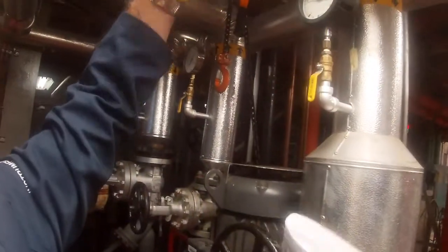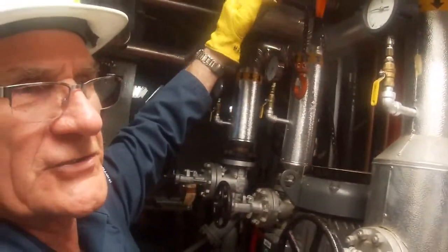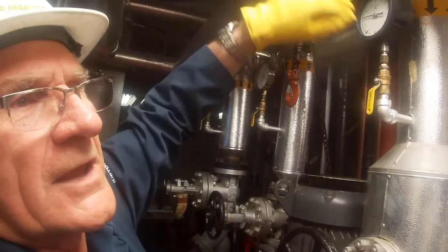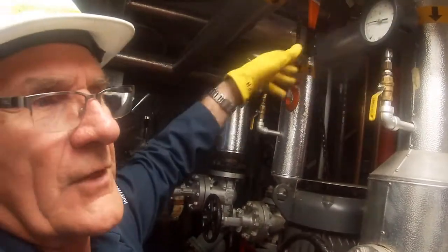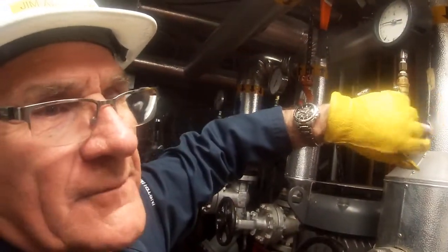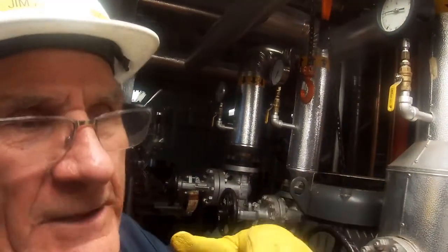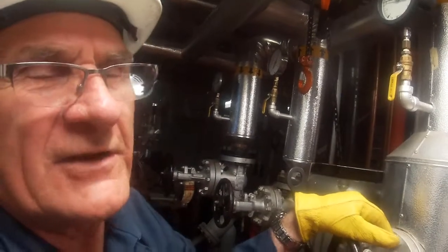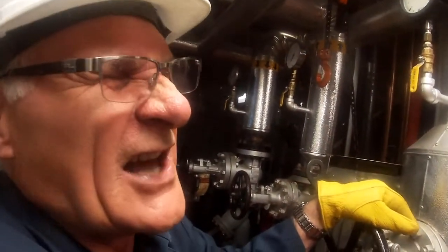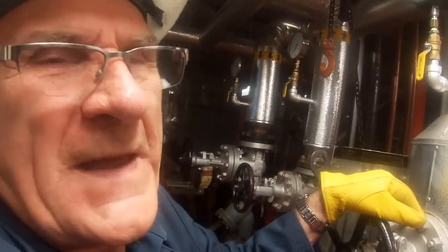The pump discharges to the header. If the pressure is over set point, there's a control valve up there that will let down the pressure back into the deaerator, back to the supply of the feed water pump. That's how we control the pressure. The pump can probably generate 2,800 to 3,000 kilopascals.